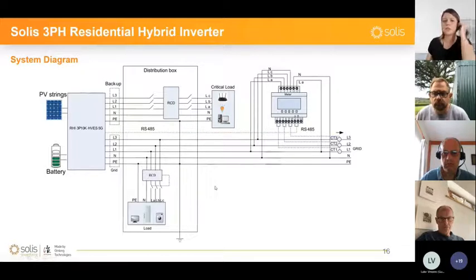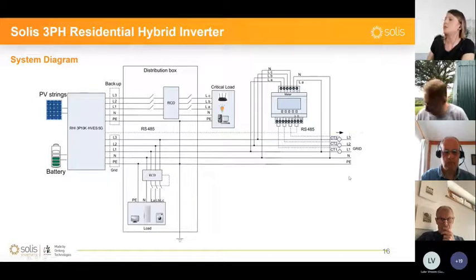The system diagram for it looks just the same. It's the three-phase system. This is the main AC grid connection point, again with the loads. At the main AC incoming power supply, we're always going to have the meter. The meter must be installed at this point in order to be able to monitor the export or the import of energy, based on which it will control the discharging and charging of the batteries.